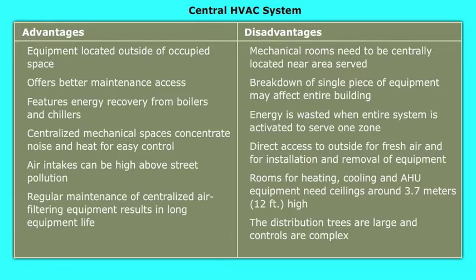An additional advantage is that regular maintenance of centralized air filtering equipment results in long equipment life. Disadvantages of a central HVAC system include: mechanical rooms need to be centrally located near the area served, breakdown of a single piece of equipment may affect the entire building, energy is wasted when the entire system is activated to serve one zone, direct access to outside is needed for fresh air and equipment installation, and rooms for heating, cooling, and AHU equipment need ceilings around 3.7 meters or 12 feet high, with large distribution trees and complex controls.